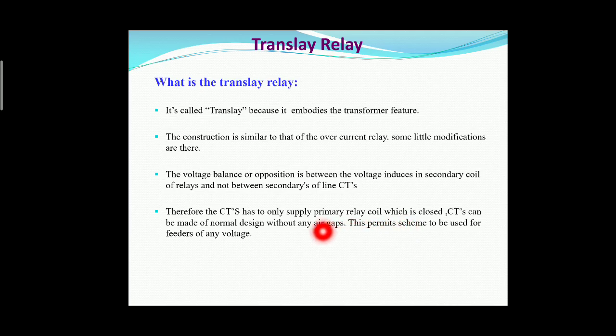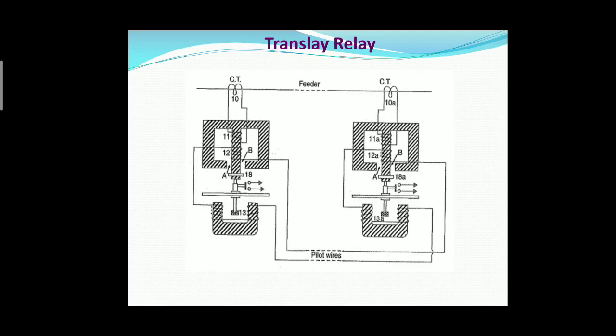This permits the scheme to be used for a feeder of any voltage. So a special design of CT is not required. That is the advantage compared to the voltage balanced differential relay. A special design for CT is not required in the case of a translay relay.